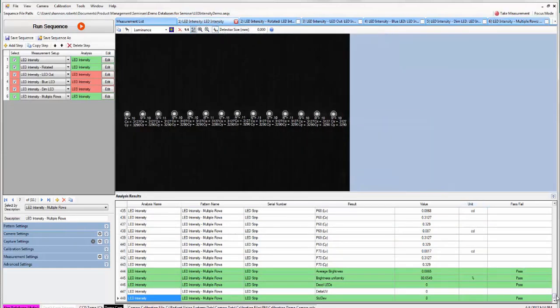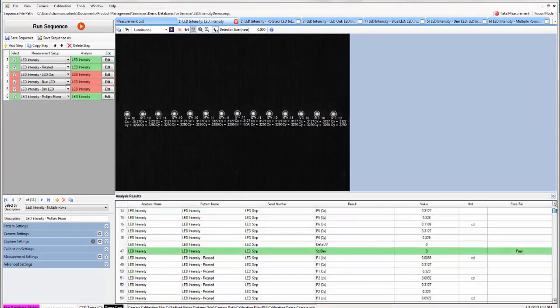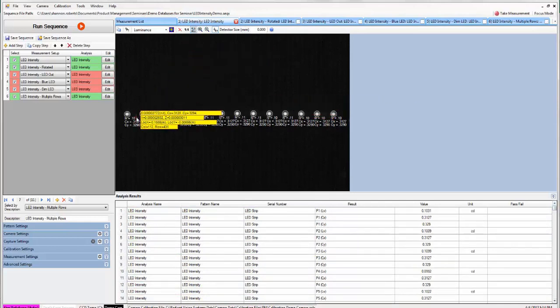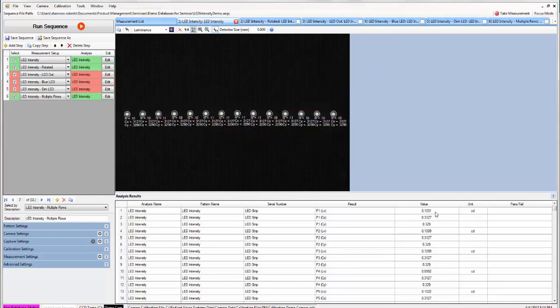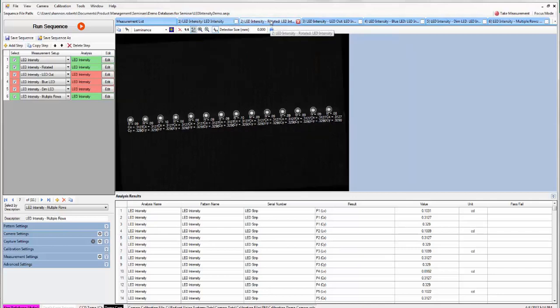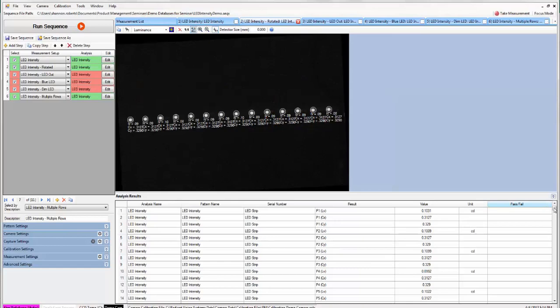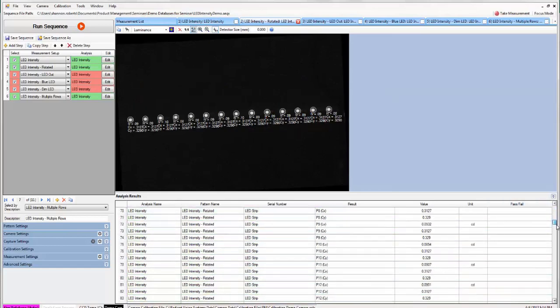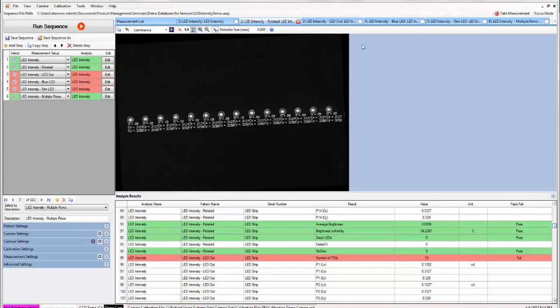So the first test here is just our basic LED intensity test and this is showing that we can auto find all 14 of these LEDs as well as output their candela and CXCY coordinates. In this case none of our LEDs failed. Additionally if our strip is rotated or in a different position we can automatically detect these LEDs in any orientation that they might be. And again here we didn't fail any LEDs in this strip.